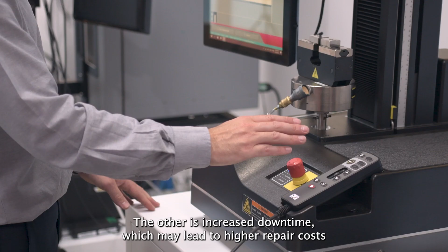An interruption to your operation can be expensive, and all this can be avoided by simply scheduling a preventative maintenance call. We suggest once every year, but it depends on the normal use of the instrument. If the customer uses the instrument 24 hours a day, 7 days a week, normally maintenance should be done every 6 months.